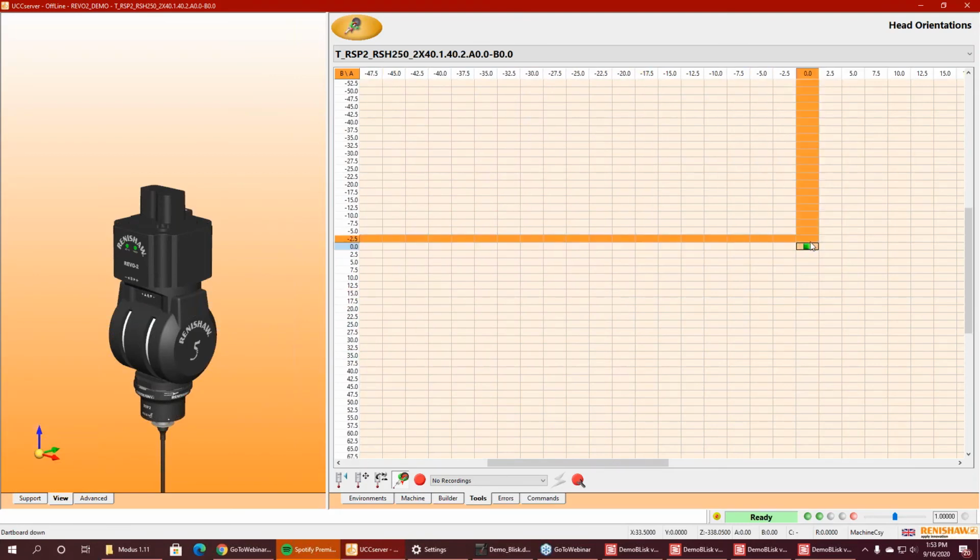And how often do you recommend that people requalify the tool? Because obviously, if I'm just using an A90, B90 kind of probe for my traditional three-axis inspection, that may only take 10 or 15 seconds or so to inspect. So if I have to requalify this whole head, is that something I have to do every hour, or is it less significant than that? Oh, it's definitely less significant. It really depends on your environment. I've seen places do it every 8 hours. I've seen people do it every 24 hours. It's definitely not something that has to be done every hour, though. Good. Well, that definitely cuts down on some time there if it's only 20 minutes for the whole head and it's only every day or so. Right.